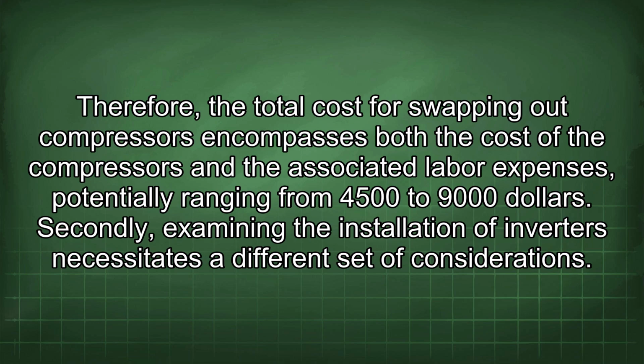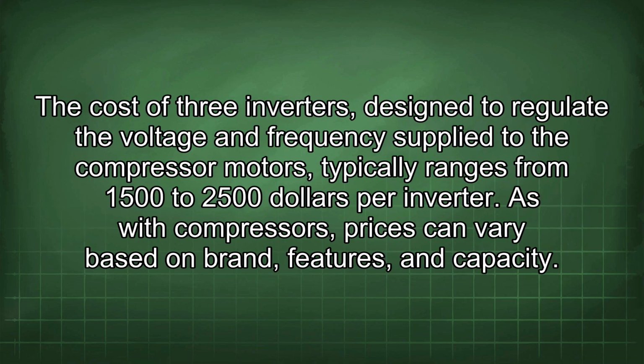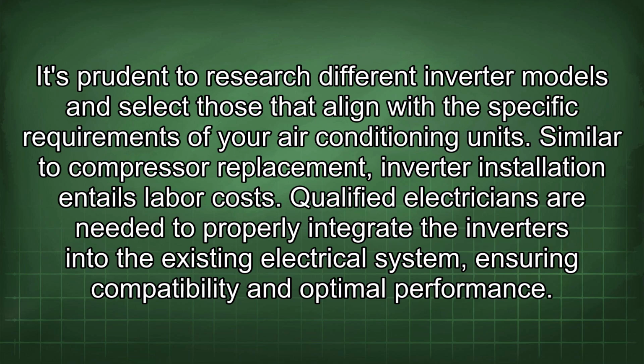Secondly, examining the installation of inverters necessitates a different set of considerations. The cost of 3 inverters, designed to regulate the voltage and frequency supplied to the compressor motors, typically ranges from $1,500 to $2,500 per inverter. As with compressors, prices can vary based on brand, features, and capacity. It's prudent to research different inverter models and select those that align with the specific requirements of your air conditioning units.